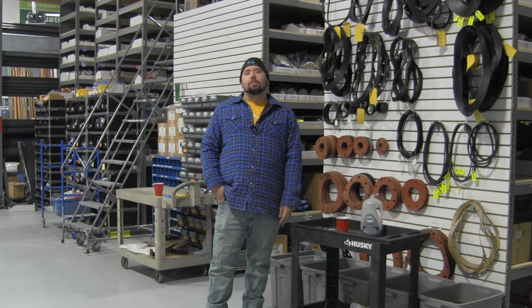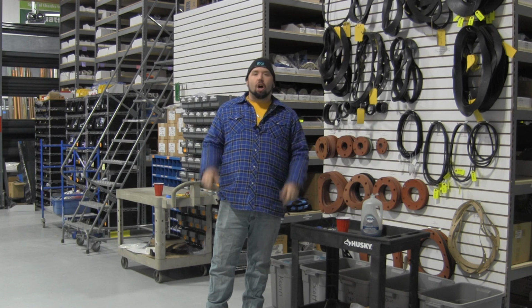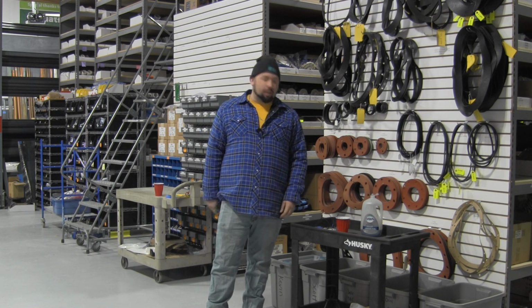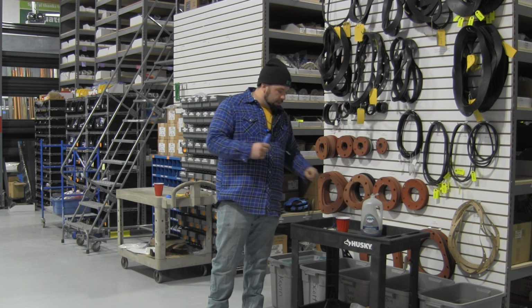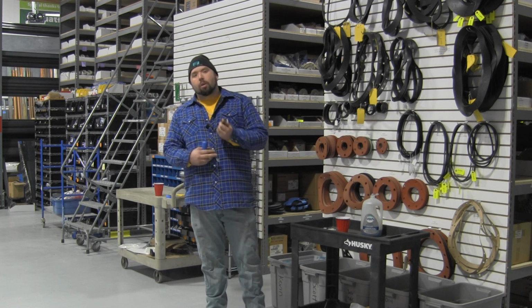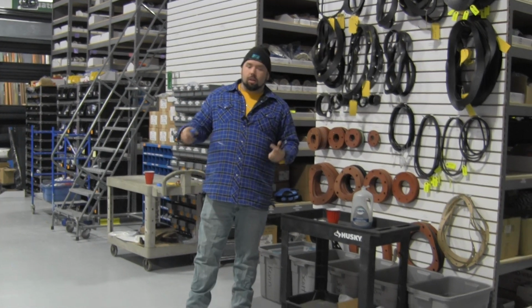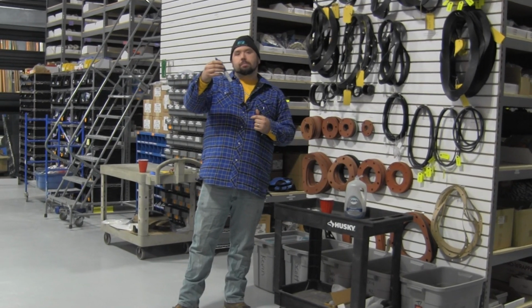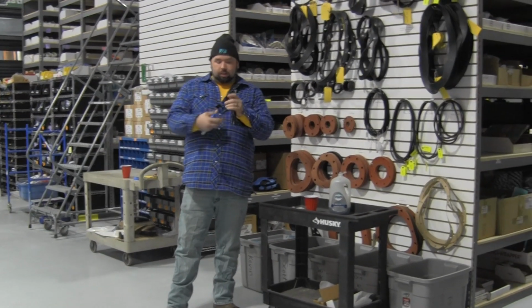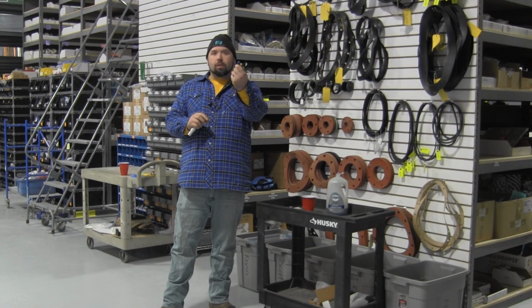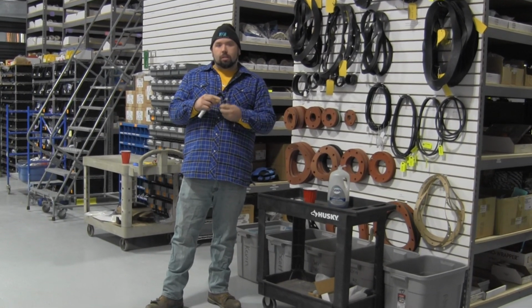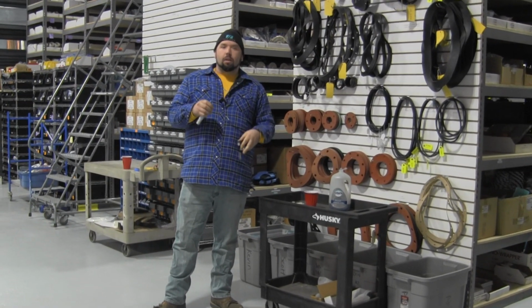First thing you're going to want to do before you even touch the probe is make sure that your flow cell is off. There's no water flow going through the flow cell. Once you confirm that you have no pressure or no flow going through the flow cell, your probe should be screwed in at the top. You're going to first disconnect the probe from the controller, from the BNC connector, right here. Disconnect that.